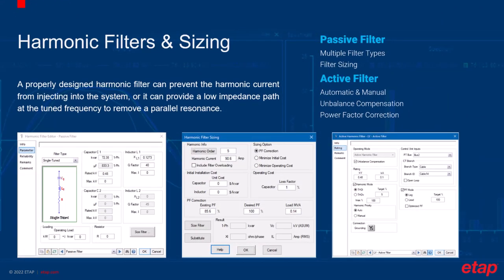too. After the harmonic load flow and frequency scan studies are performed, the harmonic-related issues should have been identified clearly. The next step is to decide on strategies for mitigating these problems and verify them. ETAP provides detailed modeling of harmonic filters and the tool of harmonic sizing. You can also model active harmonic filters and simulate its impact on harmonics, power factor correction, and unbalanced compensation.